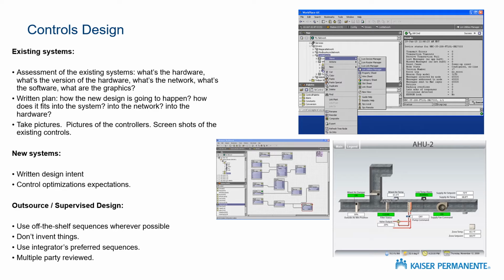It's important to keep that in mind. Our field engineers, who we're going to turn this over to, are going to spend between 500 and 1,000 hours per year logged into the building automation system. And at a hospital site, there might be 9 of those engineers. The control system and the interface of the control system is absolutely the face of your design. If the controls are bad, then your design is bad.